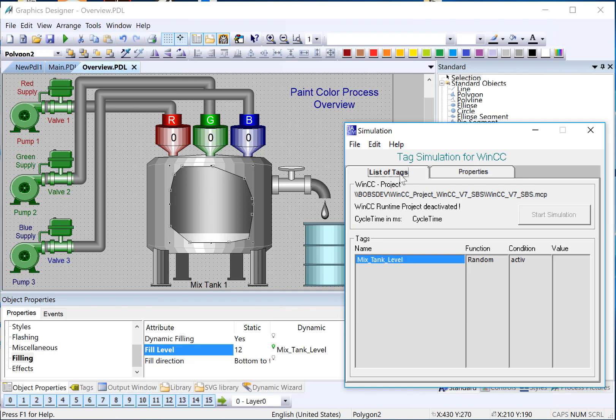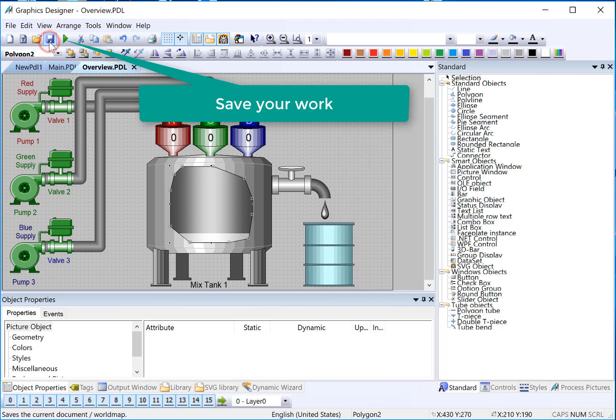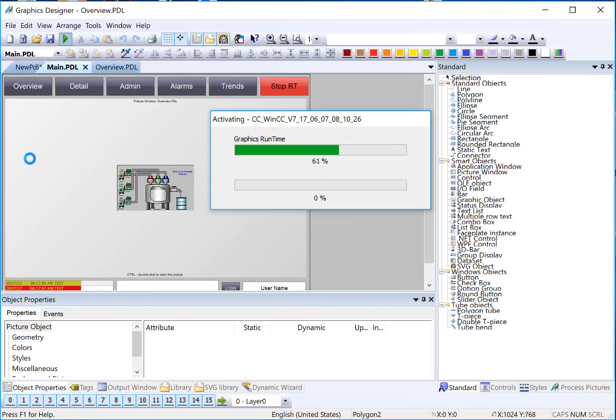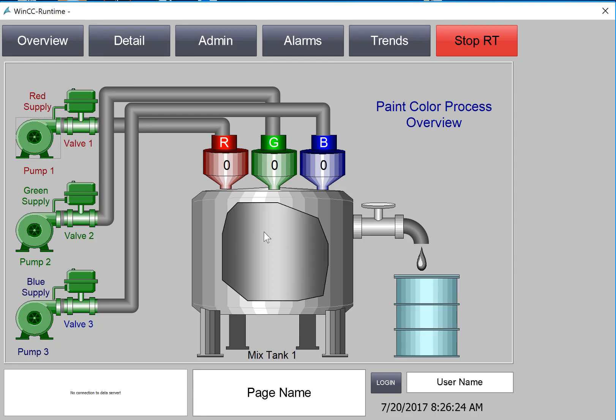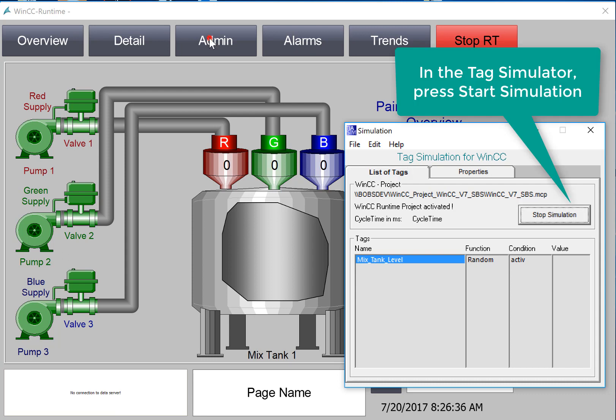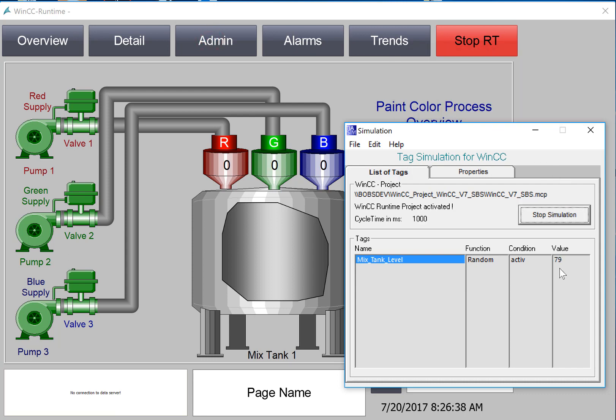Then if I go back to my list of tags, I'll see the tag here, but notice that the Start Simulation is grayed out. WinCC needs to be in runtime for this to work. I will just Save, and I will go to Runtime on my main screen. And we have Runtime up, and notice that there is nothing in the fill level. That's because the tag by default is 0. If I pull up my simulator, now we'll see that the Start Simulation is enabled, and it should start simulating that tag value.